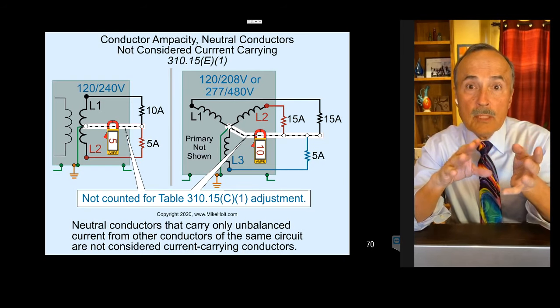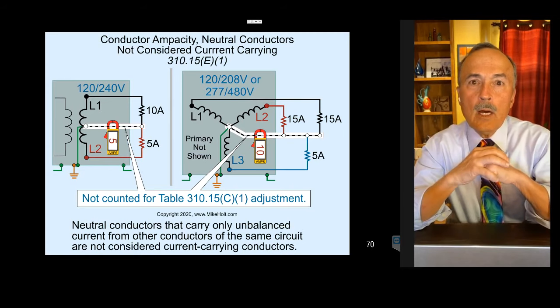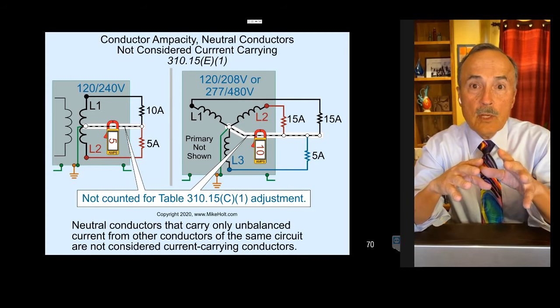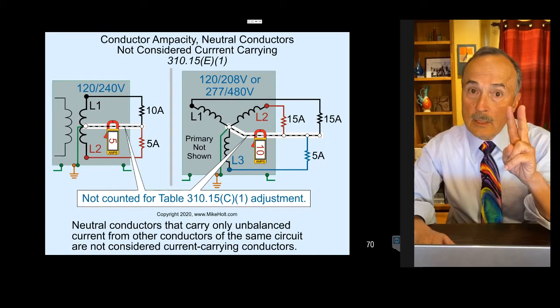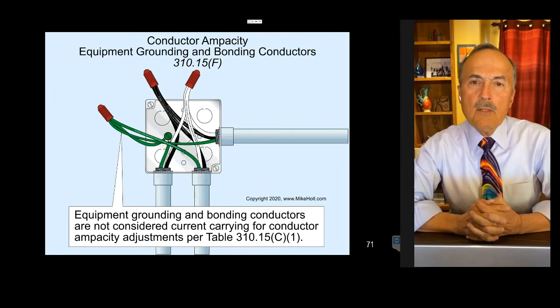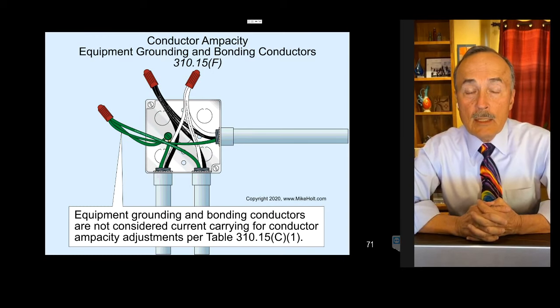Pretty much in a residence, for example, there is no nonlinear loads as far as loading concern on a 3-wire circuit, 2 hots at a neutral. Nonlinear loads only become a concern because of the odd triplen harmonic currents, which are going to be additive. We're not going to get into that. They're not going to cancel. So if you have nonlinear loads and it's a major portion of the load, like a 400 amp service with over 200 amperes worth of nonlinear neutral loads, and pretty much everything is nonlinear. If you don't know what linear is, you need to get my fundamentals book that explains that. Okay, a neutral conductor on a circuit is not considered a current carrying conductor, except on 2-wire circuits.